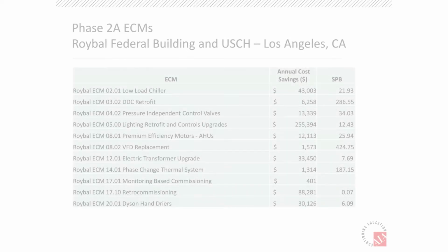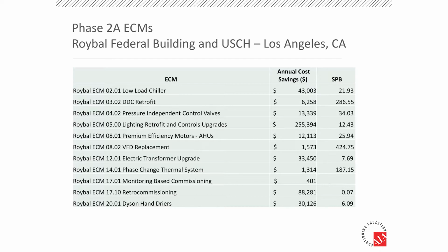Those VFDs in Roybal had failed. A significant number of them have failed. And based on the age, I'm surprised they lasted this long. So quite a few of the VFDs are actually running 100%. They're just essentially in hand mode. So we carried, again, the minimum amount of savings that GSA would allow us to put in there, and they injected capital to cover the rest. Actually, with this one, I think we blended out quite a few of the other ECMs and still managed to get it to fit in without any additional capital.